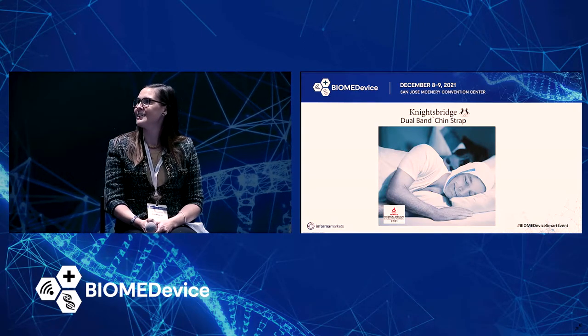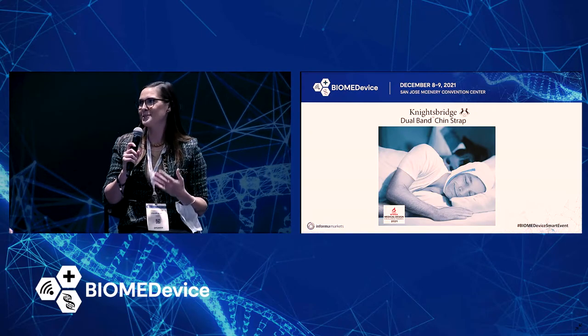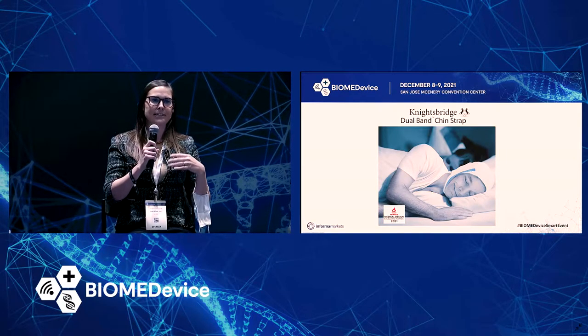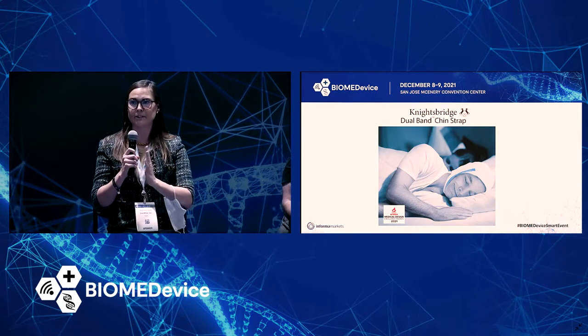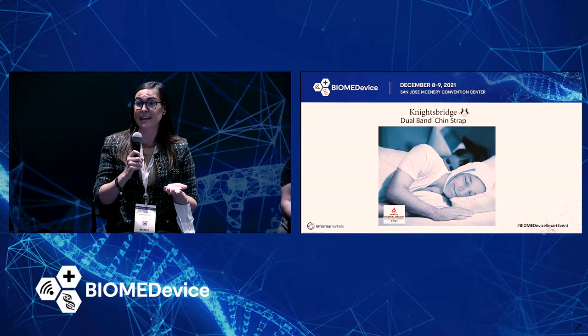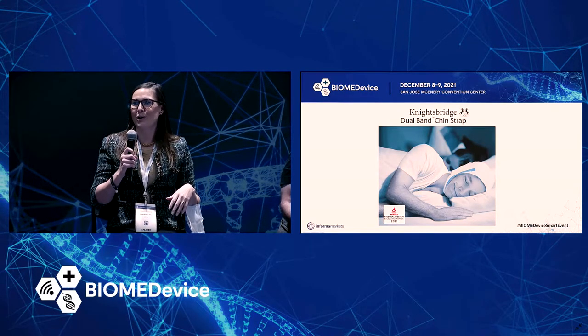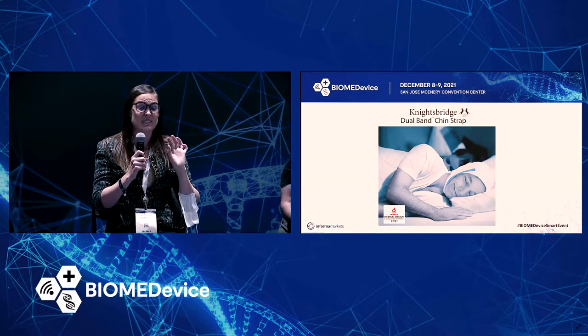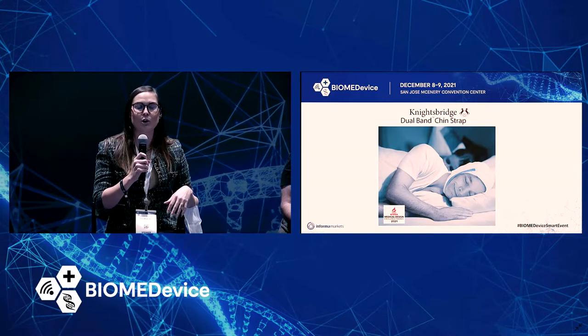Shannon, do you think it's a pitfall that some companies just take the end user's word as gospel? Absolutely. Companies so often make the wrong assumptions about who their users are or what they think. They go down a rabbit hole in the wrong direction, and at the very end of the process — maybe in human factors validation, that final study for their FDA 510K — they reveal something where they have to go back to the drawing board. It's really important to fail early and often through user-centered design, bring in end users, do a small-scale formative usability study, and make those mistakes before you're tooling up your manufacturing or doing verification testing.